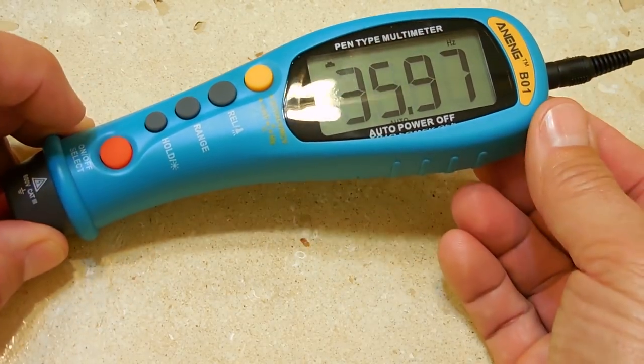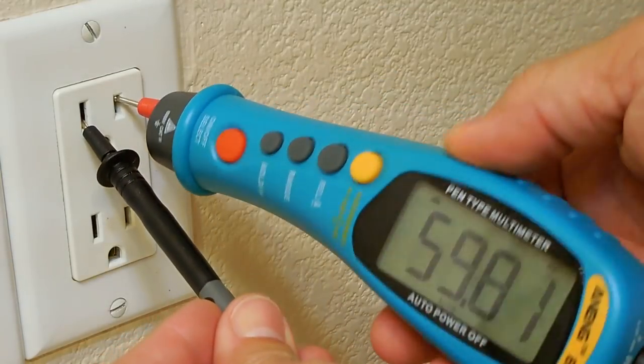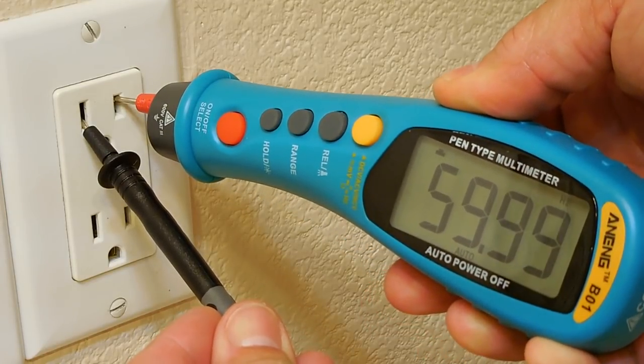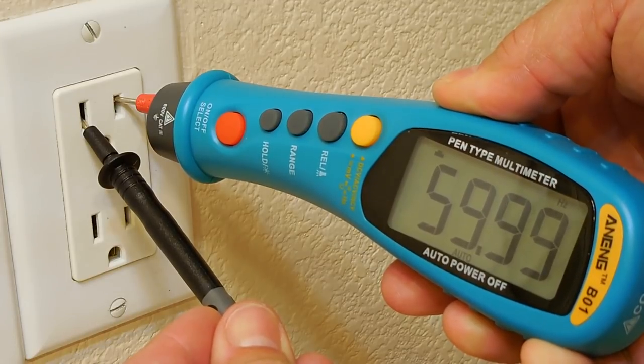Now let's measure frequency. This probe also has a cap — slide it off, insert the tip into the neutral, and connect the clip wire in. The reading is 59.99 Hz, essentially 60 Hz, which is right on.